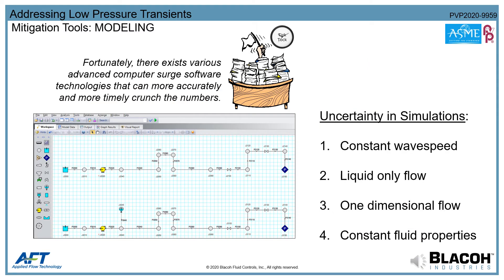So how are low pressure transients mitigated? First, they have to be properly identified. The two primary methods for predicting transient risk are computer surge modeling and transient pressure monitoring. There are two primary mathematical methods for calculating surge pressures: the method of characteristics and the wave plan method. Both require more computational effort than we have time for, even in quarantine. Fortunately, in 2020 there exist advanced computer software technologies that can more accurately and timely crunch the numbers and enable identification of effective mitigation strategies.